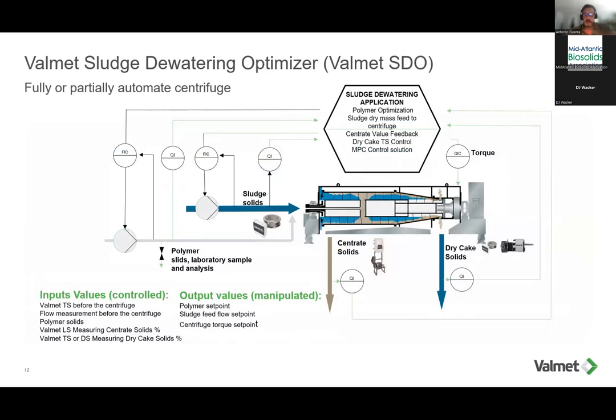If you look at the P&ID, now we have these instruments coming in and out on those streams. Again, you have your flow meter, you have your density meter on the inlet line, you have a measurement available to measure the solids on the centrate, and you have a measurement available to measure your cake dryness, your cake solids. So this control package, called the Valmet Sludge Dewatering Optimizer, takes into account all those measurements that we have available to us and controls the output values. We know the concentration coming into the system, we know the flow, so therefore we're enabling a mass flow equation. We know the polymer solids coming in, we know the centrate solids coming out of the system, and we also know the cake solids coming out of the system.